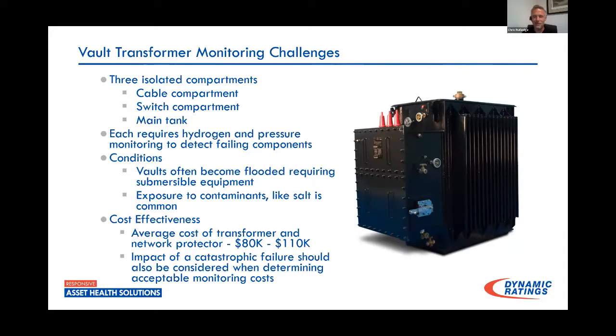I mean, the moisture level in oil is definitely something you need to know about your transformer. But in my experience, when I found that a transformer is wet, that's really a big headache at that point to save it. When you get into a larger substation transformer, of course, you can vacuum process with a hot oil bath and vacuum process that transformer until you can get it dried out to some degree.